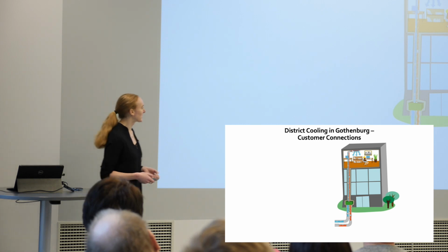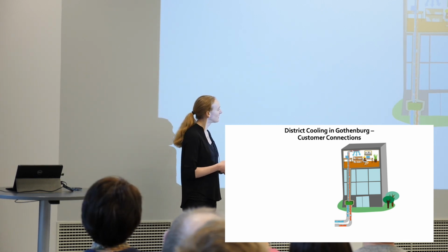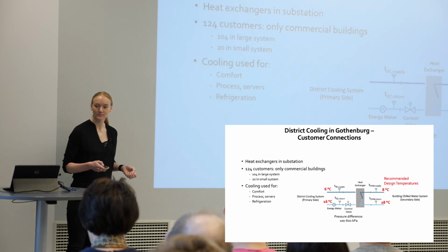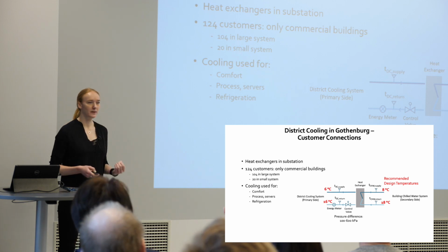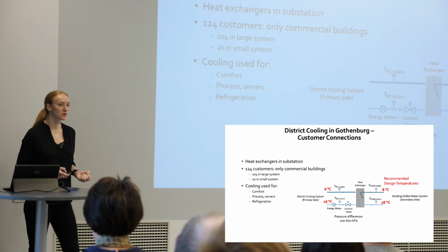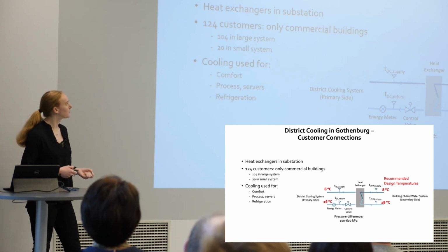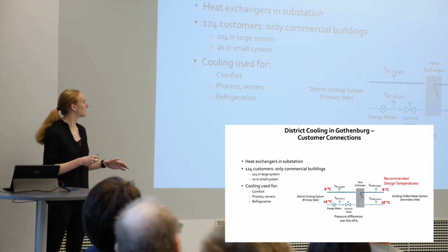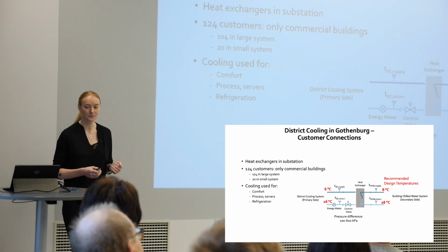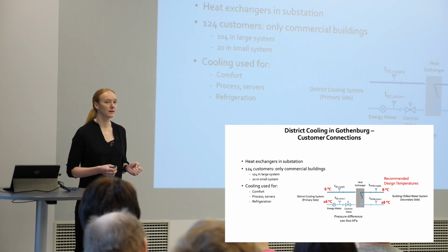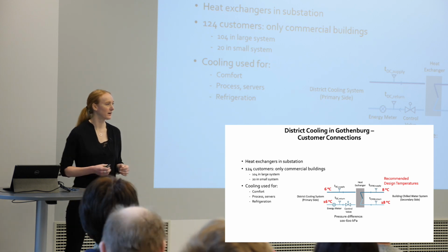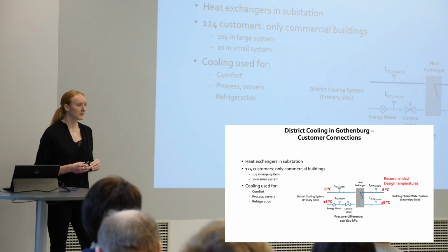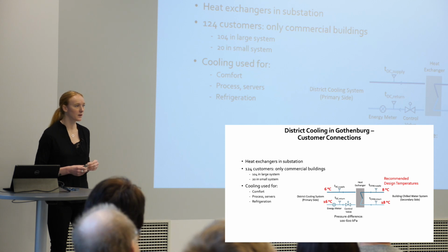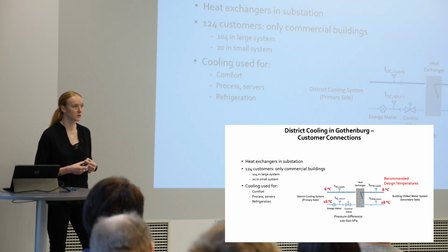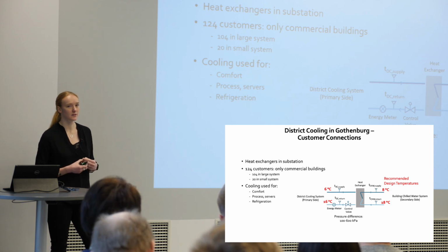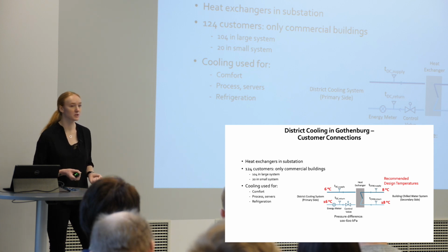Now I'll move over to the customer connections and mainly what happens here in the substation. In all the customer substations or building connections, there are heat exchangers. There are around 124 customers in both systems, roughly 104 in the larger and around 20 in the smaller. It's only commercial buildings that have district cooling in Gothenburg, no residential, and right now I don't think there are any plans to connect residential. These buildings use the cooling mainly for comfort cooling, but also for some process cooling and servers. Some customers use it for refrigeration, mainly to cool the condenser side of different refrigeration machines.